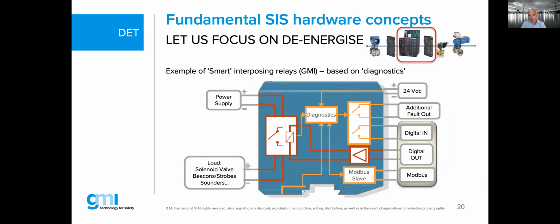What is now so special about a simple interposing relay? Well, interposing relays are not as simple as you may have thought, because they are full of intelligence inside that little box, inside the little relay. And the intelligence is known as a kind of diagnostic. That means the signal that needs to be sent out to the field is also monitored and fed back into the diagnostics intelligence.